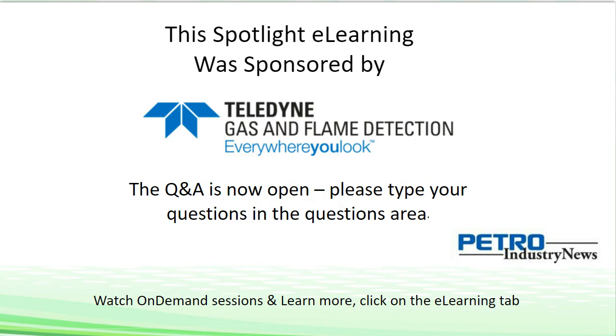Again, personal protective equipment: if you are wearing a gas detector that's simply an oxygen monitor, and you're working in an area where nitrogen is present or oxygen is present and no flammable gases are present, then the type of monitor that you may wish to purchase or specify, or perhaps you're working in a hospital where oxygen is being used but no flammable gases are present, the type of sensor, the personal monitor that you may wish to use may be very, very different to the type of sensor that you may wish to use if you're walking around on an oil refinery, which is clearly a hazardous area with lots of flammable hydrocarbons present. So that would be my quick answer to that question. Maybe Francois also has some additional technical insight.